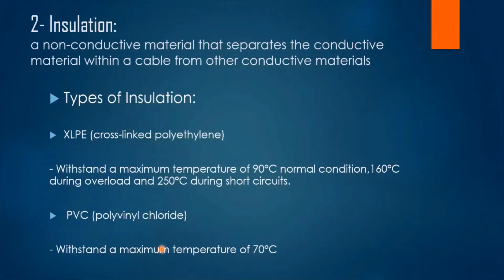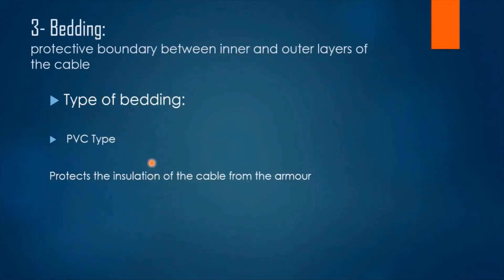However, PVC cannot withstand as much temperature — it can withstand a maximum of 70°C. The third layer is the bedding layer, which is a protective boundary between the inner and outer layers of the cable. It is always PVC type, and its main aim is to protect the insulation of the cable from the armor.